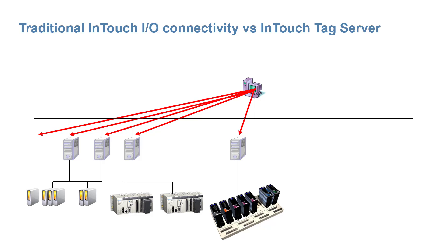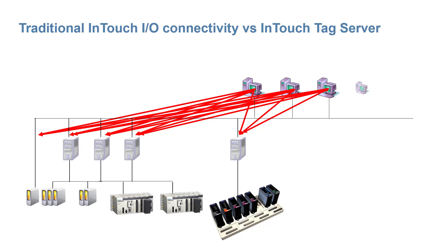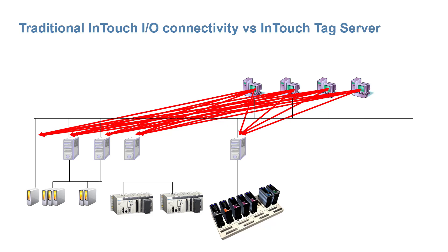Each visualization node requires at least one or more connections to each source of data. Adding additional operator stations means the demand may swamp older equipment, which may lack caching or queuing features for regulating additional demand. If a business grows from just a couple of workstations to an enterprise, it's possible even the plant floor will suffer. The network burden is one-to-many for every visualization node added.